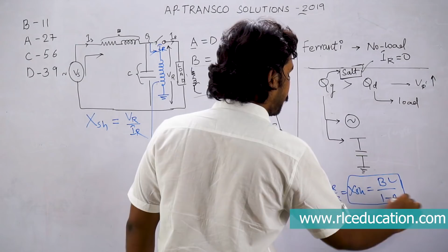Because this is the only element connected at the receiving end, if I find this ratio VR by IR, I get the shunt reactor required. Taking VR common, VR(1 - A) equals B*IR. So VR by IR, which is the shunt reactance to be connected for the Ferranti effect, equals B by (1 - A). So just by using the ABCD parameters, you can estimate how much shunt reactance to connect at the receiving end to neutralize the Ferranti effect.